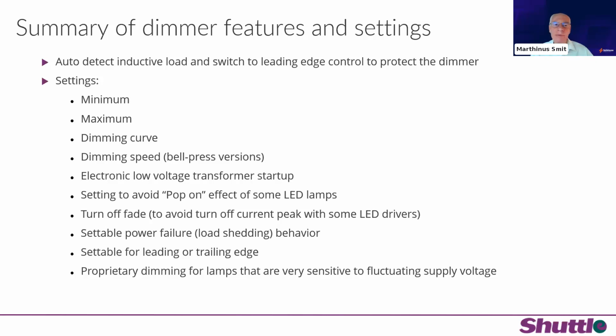Nowadays in South Africa, load shedding is becoming the norm, and many people require different behaviors from their dimming circuit when the power returns. Some people want the dimmer to always remain off. Some people want it to come on at minimum intensity, and so on. So ideally, your dimmer must be able to adjust that power failure behavior. Like I said earlier, it must be suitable for leading and trailing edge dimming, and then ideally, for the emerging problem where lamps are very sensitive to supply voltage fluctuations, the dimmer must have some sort of setting to address that.